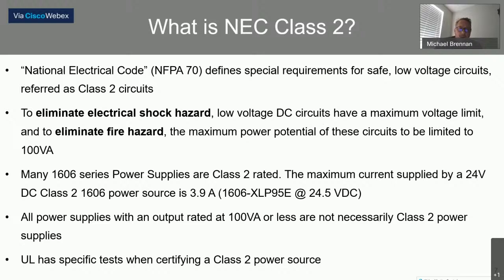Now, many of the 1606 power supplies from Rockwell Automation are Class 2 rated, but not all. Not all 4 amp and below 1606 power supplies are Class 2 supplies. So one of the things that's very important to know is if you have a requirement for a Class 2 circuit, that you purchase a Class 2 power supply, and it will be labeled on the individual product. UL has very specific tests that include additional circuit protection for those individual devices.